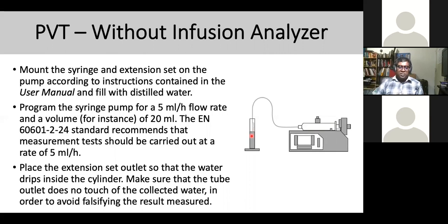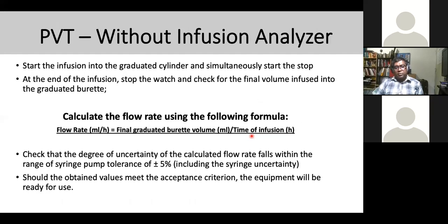This is the diagram of the connection. Once you do the setting, all that, you can start to infuse, and you see gradually the fluid will travel to the cylinder, and by using the stopwatch, you monitor the delivering time. So this is the calculation for the flow rate using the formula: flow rate in milliliter per hour, final graduated burette volume, and time of infusion. So you take your time and you take the volume and you divide, you get the flow rate in milliliter per hour. And tolerance should be plus minus 5% from the reading. So this is how you do it actually.